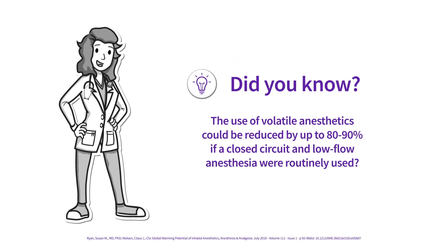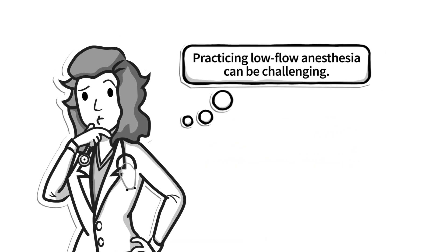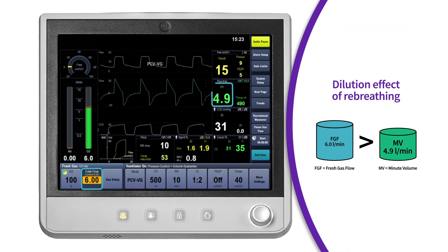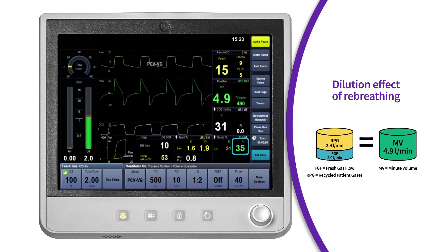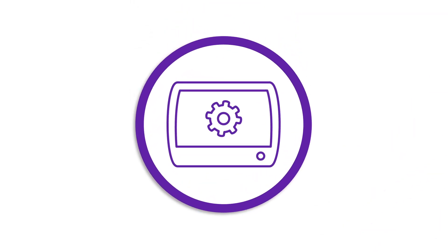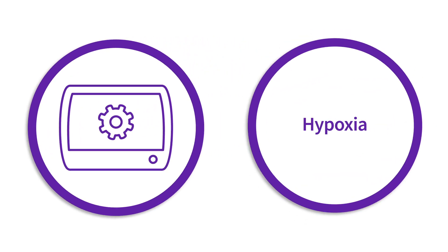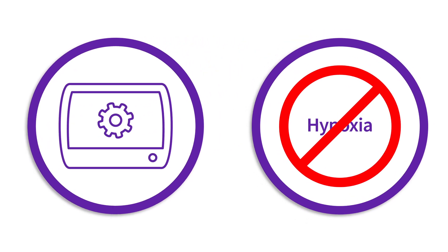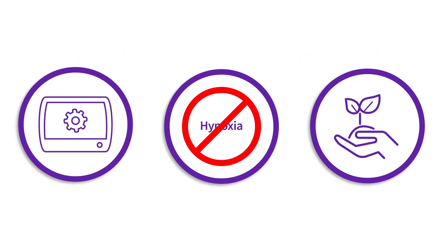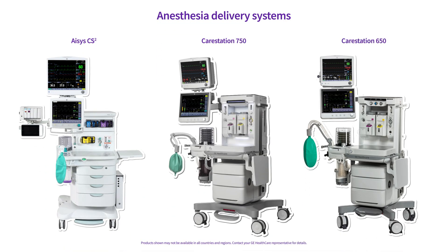Did you know that the use of volatile anesthetics could be reduced by up to 80 to 90 percent if a closed circuit and low flow anesthesia were routinely used? However, practicing low flow anesthesia can be challenging. As fresh gas flow is reduced, more recycled gas makes up the patient's delivered minute ventilation. As more recycled gas is consumed, the FiO2 decreases because oxygen is not being replenished from the fresh gas flow. What if you had a tool that could help guide you with lowering your fresh gas flows to help mitigate the risk of hypoxic delivery, avoid excess fresh gas flow, and help reduce the environmental impact of anesthetic agent use? Then EcoFlow may be your solution. This video will discuss the EcoFlow software found on specific GE anesthesia delivery systems.